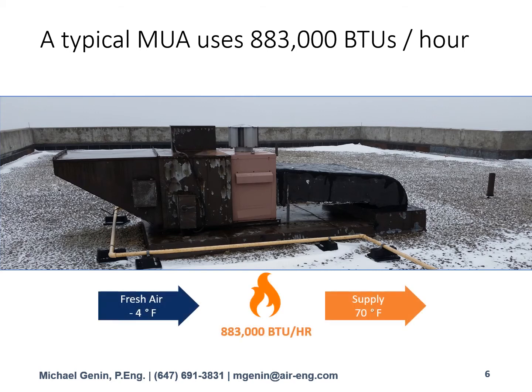And what is happening is fresh air is being brought in at our design condition at -4 Fahrenheit. And we are burning 883,000 BTUs per hour of natural gas. In this case, this is for a system that's 11,000 CFM. And we've decided on having a supply temperature of 70 degrees Fahrenheit as our design of room neutral air.